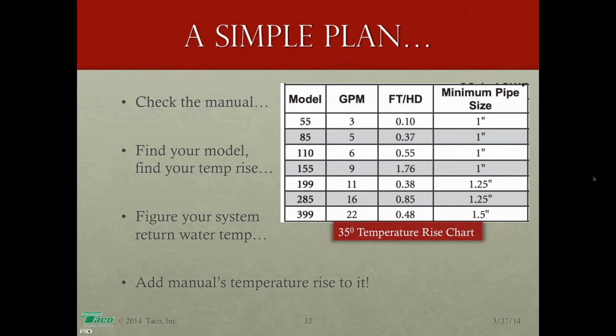Okay, a couple quick questions here. This is from Troy. You may have answered this, but I can't stretch out my GPM by playing with my delta T, and most mod cons come with a constant speed pump. Should I use a Bumblebee as a boiler pump? I'm going to say you probably shouldn't. I would say you should use what the boiler manufacturer tells you to do. When you start playing games out in the field and something happens, not a good thing.